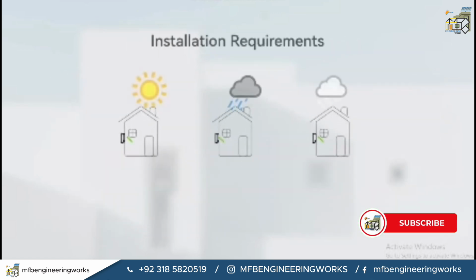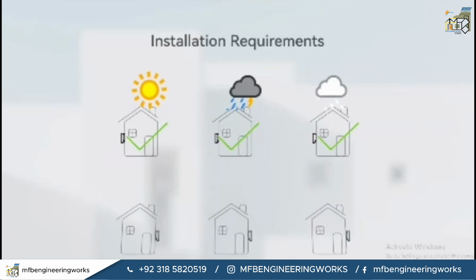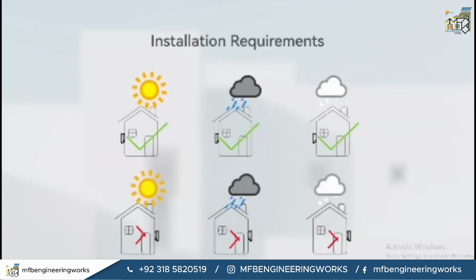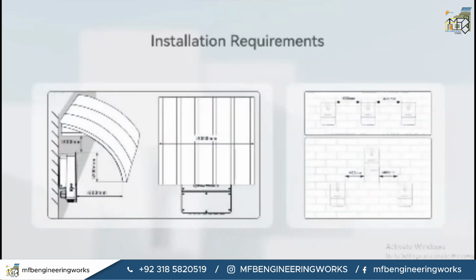As it is an IP66 rated inverter, it should be installed in an appropriate environment. It should not be exposed directly to sunlight, rain or snow. It is better to install the inverter in some awning area where sunlight, rain and snow do not directly fall on it. If you are using multiple inverters at the same place, it is recommended to maintain spacing between them. For the installation of the inverter, we require some tools which are shown on the display.